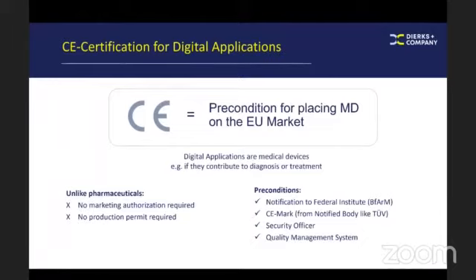The digital application, of course, needs a CE certificate. Now, all of you know that a medical device in the EU market requires a CE mark. And this is different from the situation at the PMDA or with the FDA in the US, because the system to establish a CE mark is a system based on private law. The law within the EU serves as a framework, and the companies make contracts with the notified bodies about the service to get a CE mark for a product.